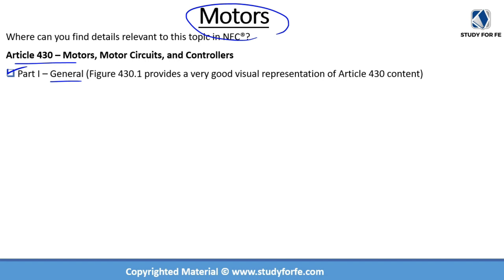Part 1 is titled General. It contains general code requirements for motors. Within Part 1, on the very first page, we have Figure 430.1, which provides a very good visual representation of Article 430 content. It's basically a diagram showing the motor feeder, short circuit and ground fault protection, motor disconnect means, and so on, cross-referencing other sections within the article. It's a very good visual representation and provides a very good overview.